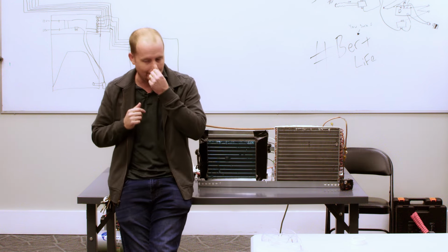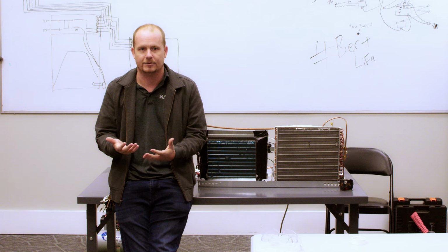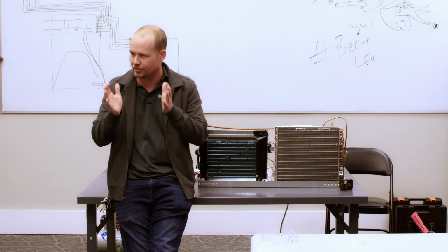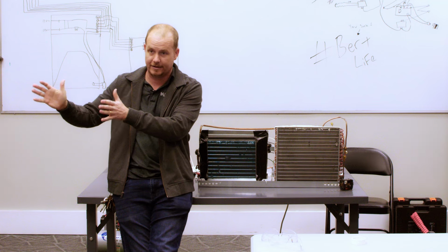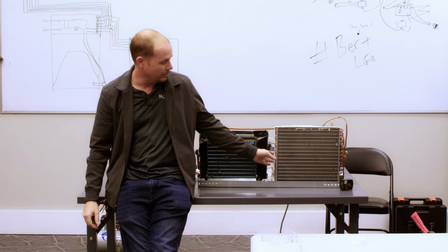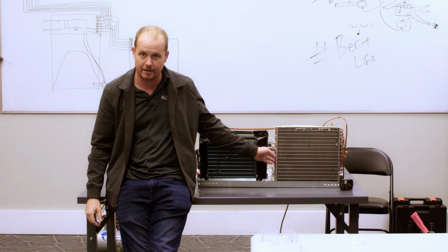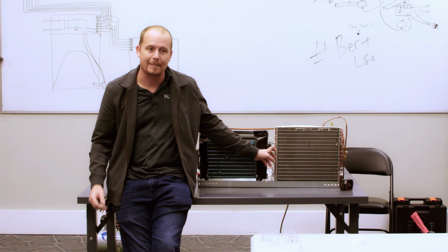And this is what I always want to get through when we talk about saturation temperature, is that it's not just some ambiguous number that's meaningless. It actually means something. When we're doing it on the suction side, that's our evaporator temperature. It is the temperature at which the refrigerant is evaporating in the evaporator. And when I'm looking at condensing temperature or liquid saturation, it's the temperature at which it's condensing. Right, exactly. And why does that matter to us?